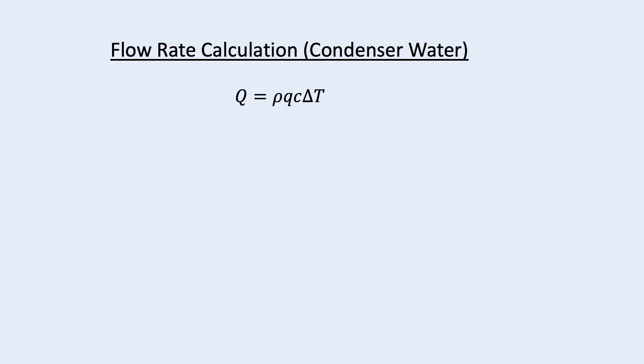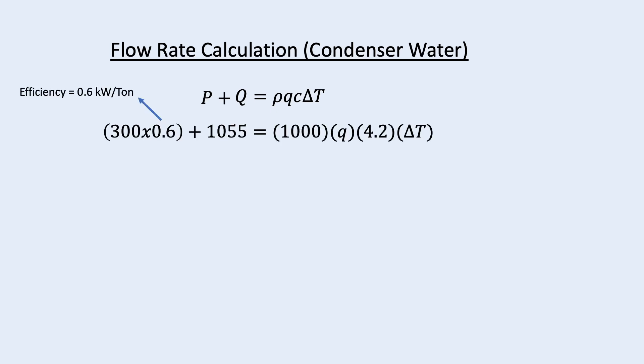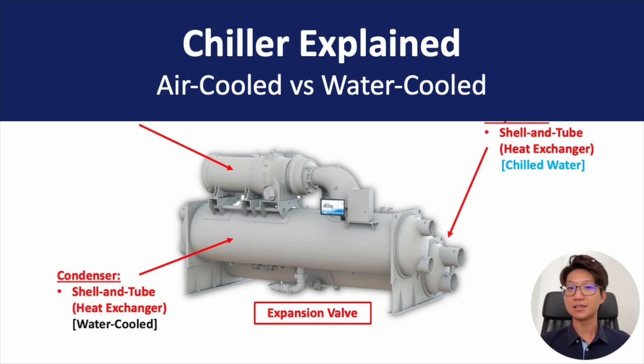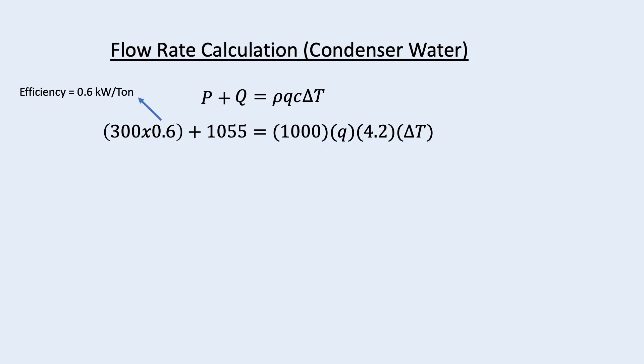For condenser water flow rate, the calculation is the same except we need to include the heat of the chiller. We use the efficiency of the chiller to estimate this heat. In my video about chiller, I explain why water cool chiller is more efficient than air cool chiller. The efficiency of a typical water cool chiller is about 0.6 kilowatt per ton.